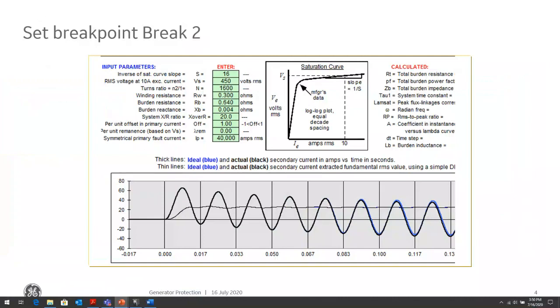So now I know that CT is okay. How do I determine, how do I set the breakpoint? The second breakpoint is where slope 2 begins. And remember, that should be set for an external close-in fault where my CTs are going to see the maximum amount of fault current. So I want to set that with some sort of margin within my maximum fault current. In this case, I dropped it to maybe 40. Remember, it was 50,000 amps. I dropped it to 40.